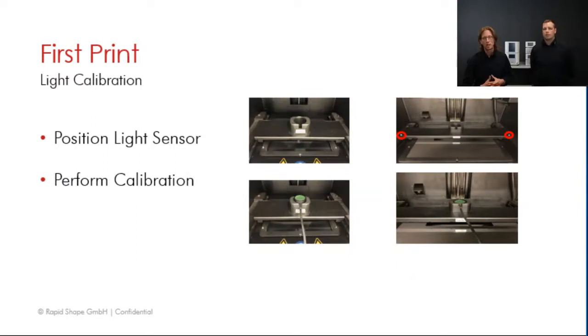Here I have an example, or basically two examples. The one on the left-hand side is for the 20 plus machine, and the one on the right-hand side is the 30 plus machine. So, as I mentioned, first you insert the calibration tool followed by the light sensor. Make sure that the glass side of the light sensor is facing downwards, so that we can measure a proper value.